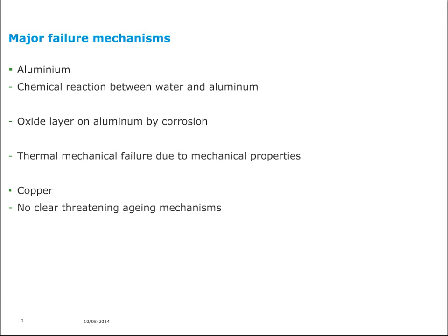Thirdly, the thermomechanical failure due to the mechanical properties. The coefficient of expansion, I showed you that in the previous slide, is higher for aluminum than for copper. That means when you have thermal cycling in a cable, the aluminum conductor is expanding and contracting more than the copper. And that results in mechanical forces, particularly at the joint place. And that can also result in failures. In general, when there is a lot of expansion, you have a lot of thermomechanical forces, and that can be resulting into failures.